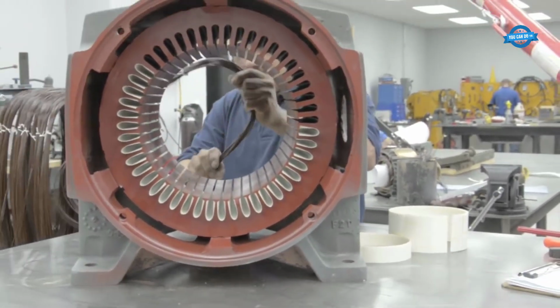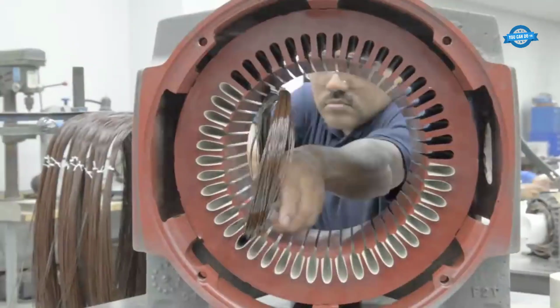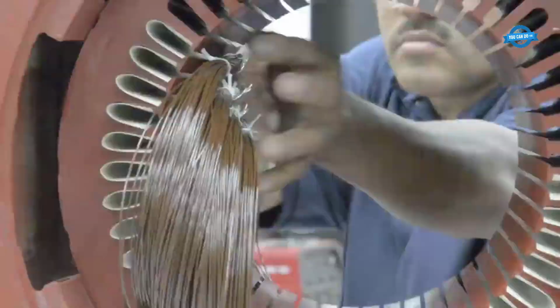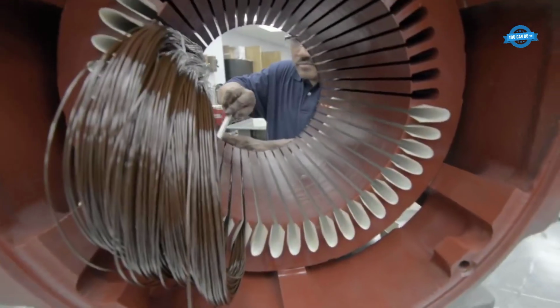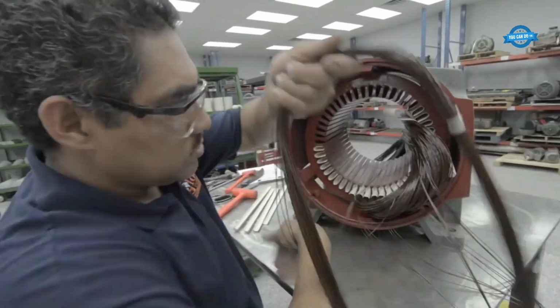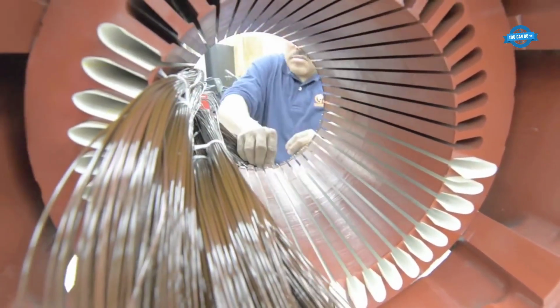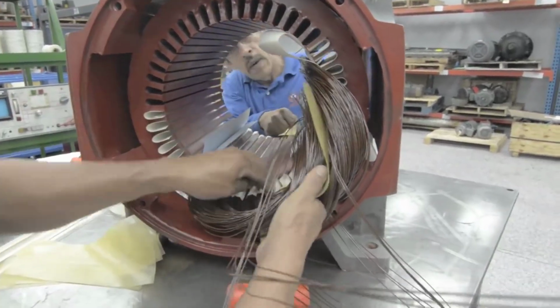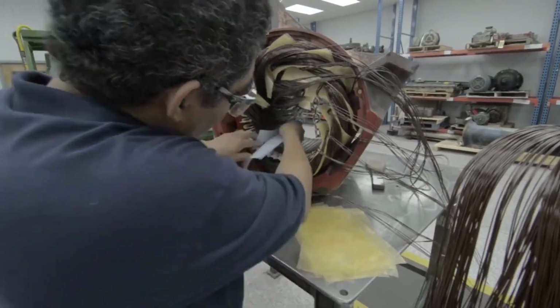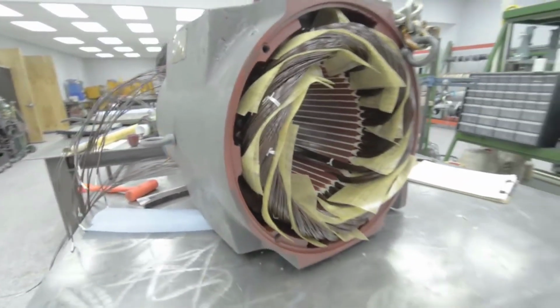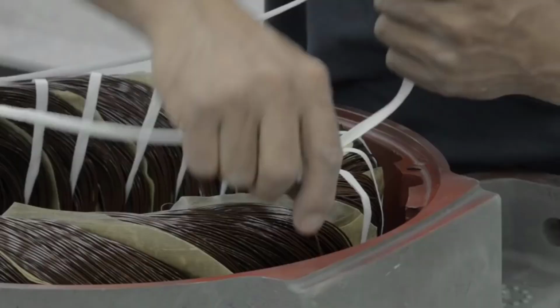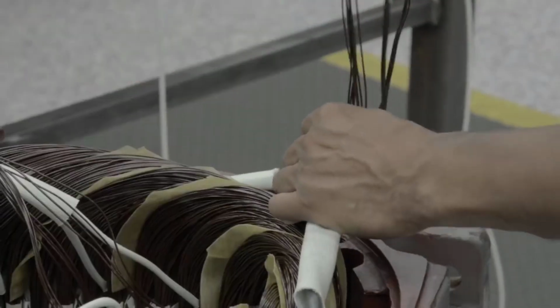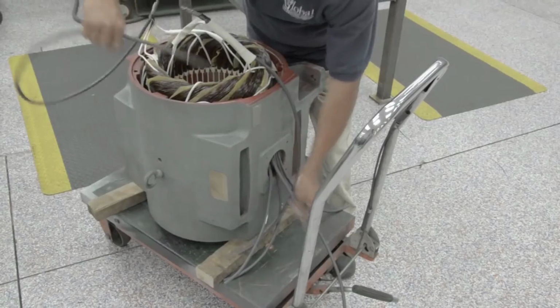Technician will need 48 coils in 12 groups of 4. The coils are then added to the stator slots and grouped according to the motor's configuration. After the coils are in place, wedging is added to prevent rotor to winding contact and to further insulate. Then the winder technician adds lacing to add strength and stability to the newly formed windings.